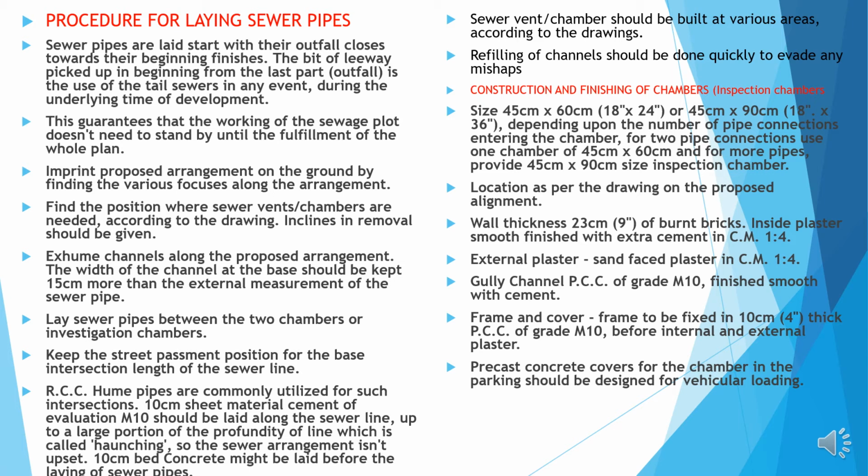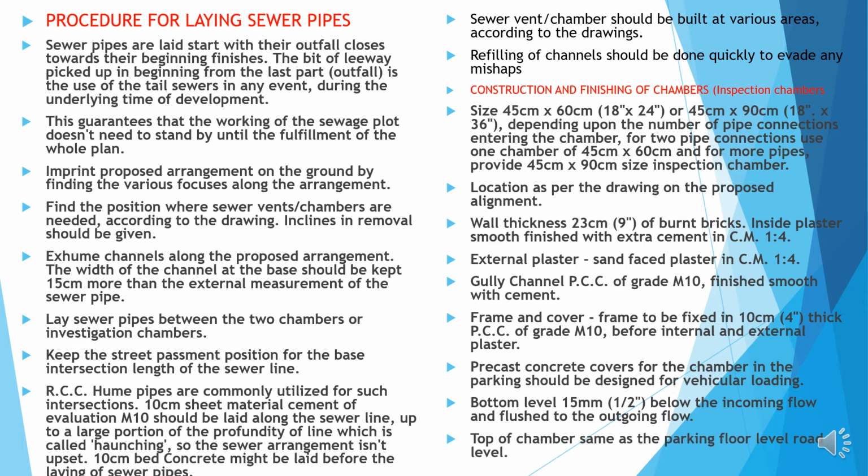Precast concrete cover for the chambers in the parking area should be designed according to the design calculation of the vehicular loading. Bottom level should be 15 millimeter below the incoming flow and flush with the outgoing flow. Top of the chamber same as parking floor level or road.